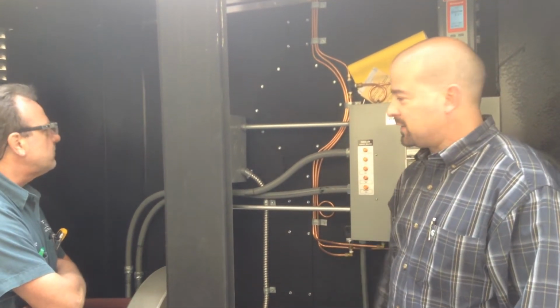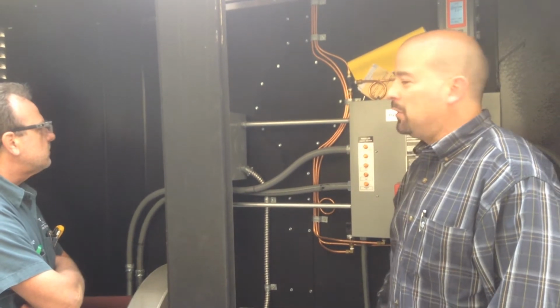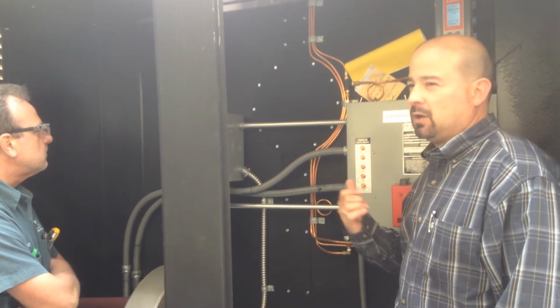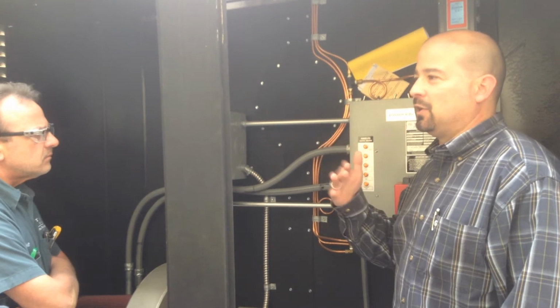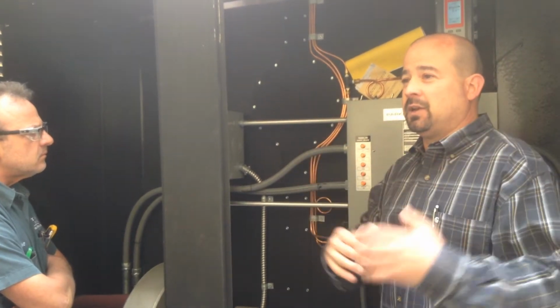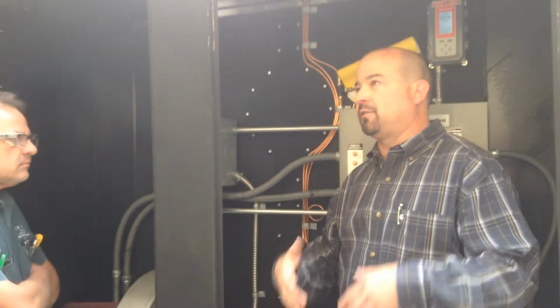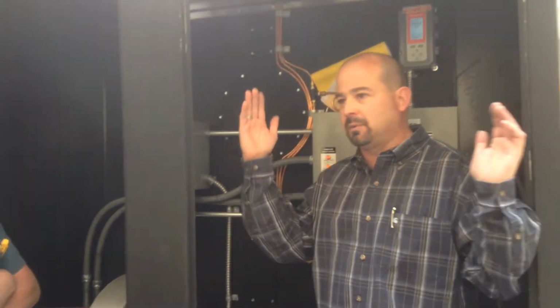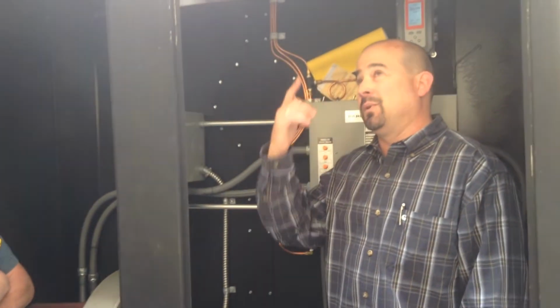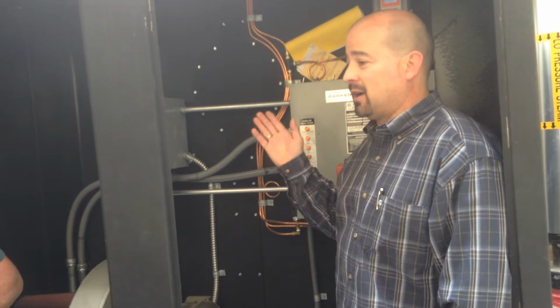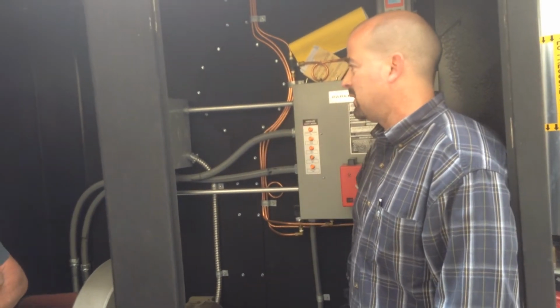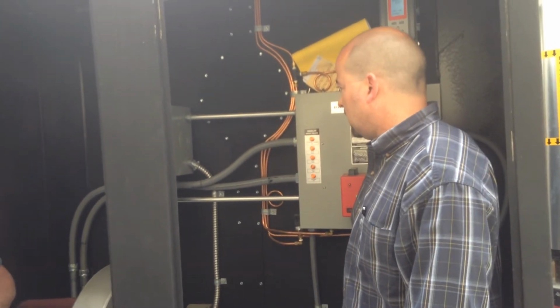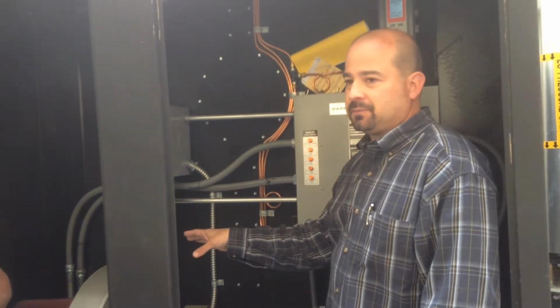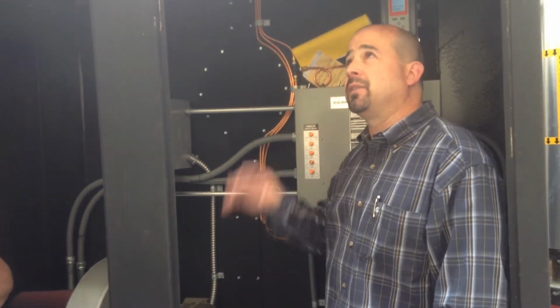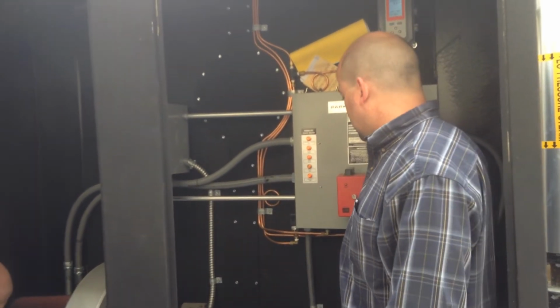that's what low fire is going to sound like. Most of the time I'm thinking this thing's going to be running in low. It's going to be not much of a load. It's a pretty consistent load. You know, it's not like when you first turn it on, if the building's cold, obviously you're going to be ramped up in the high fire. But with the building the way it is, it's probably just going to come on and off in low and maybe hover at 25%, something like that. So that's what low fire sounds like. Pretty quiet, so I don't think you're getting any complaints on noise.